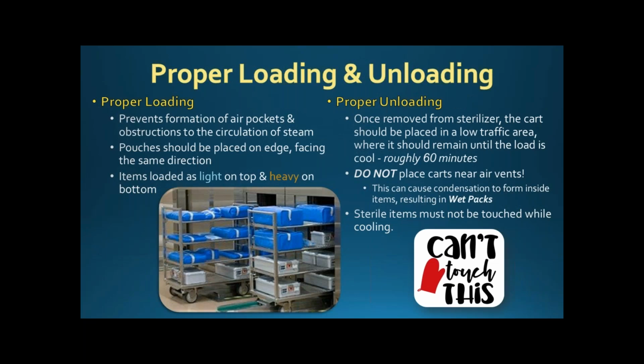Proper loading and unloading. When you properly load, you see every single set is spaced appropriately. When I was taught SPD, I was taught that you should do the hand test. Your hand should be able to pass between all the different sets in there for adequate spacing so that you can have full penetration. And once they take the load out of the sterilizer, you want to place the cart in a low traffic area where you don't have direct exposure to vents and things like that, because with cold air and hot instruments, you have water in the air, and it can lead to condensation forming, which will result in wet packs and reprocessing of everything.